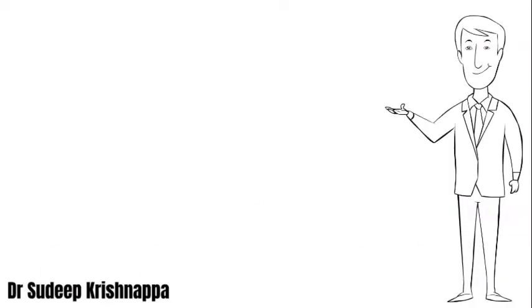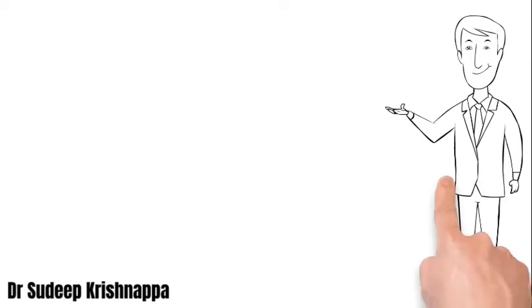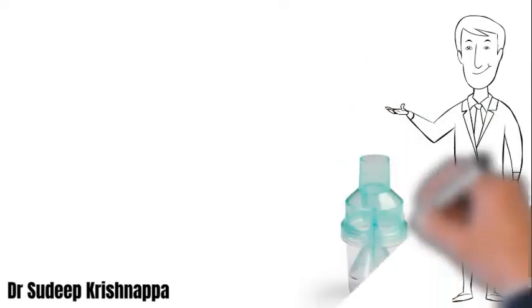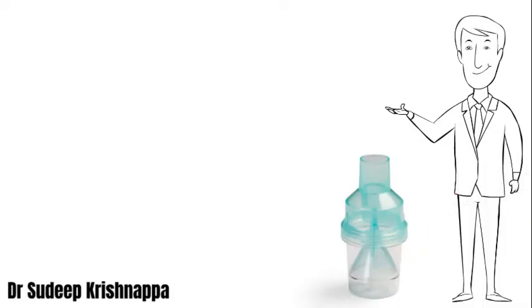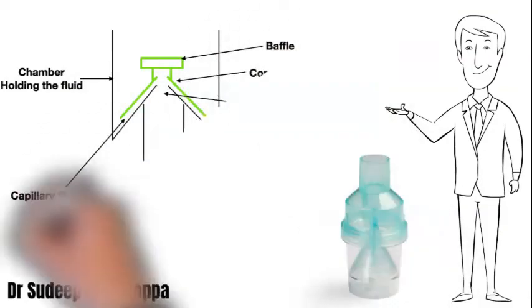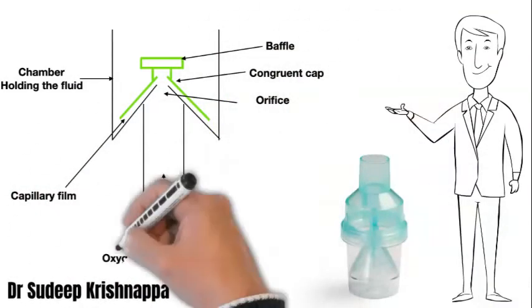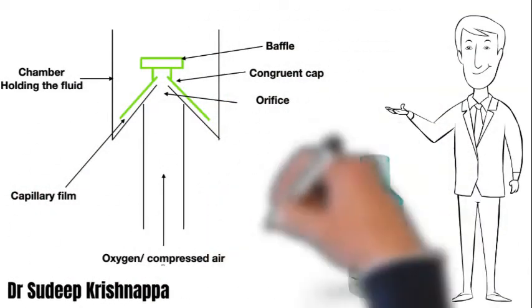As mentioned earlier, these Venturi devices come in various shapes depending on the manufacturer's specifications. Here we have chosen one such device — only the nebulizing chamber is highlighted and the rest of the components are essentially the same. This line diagram represents the internal mechanism of the nebulizing chamber.